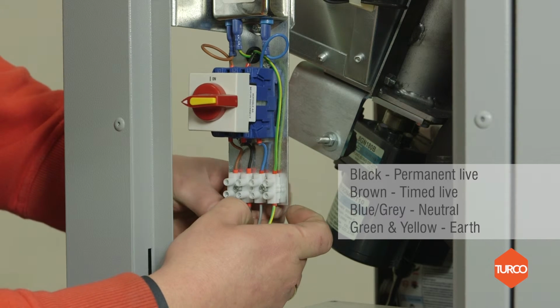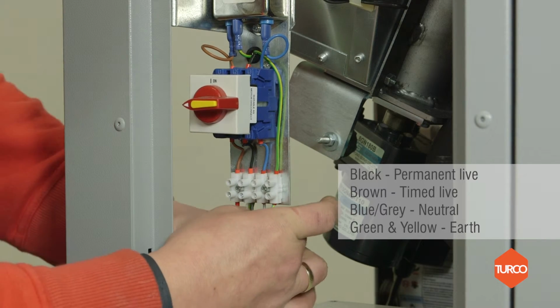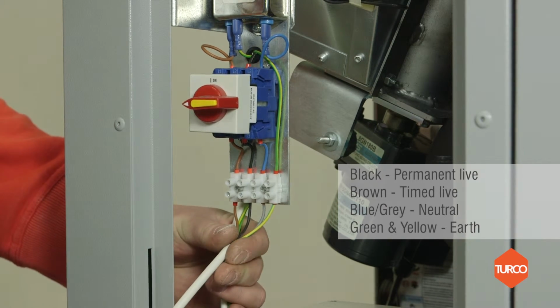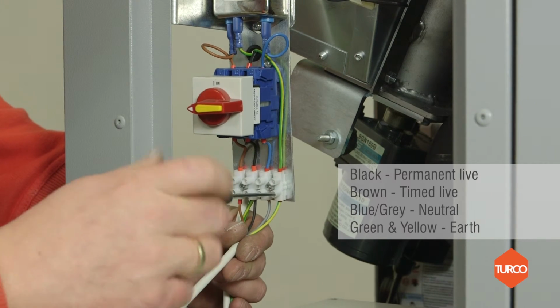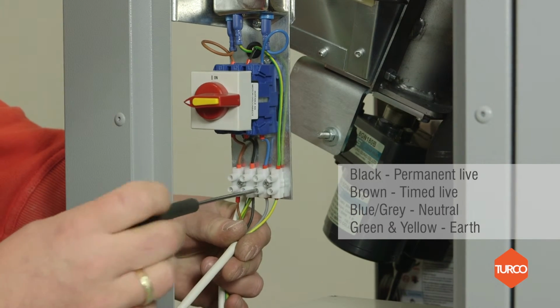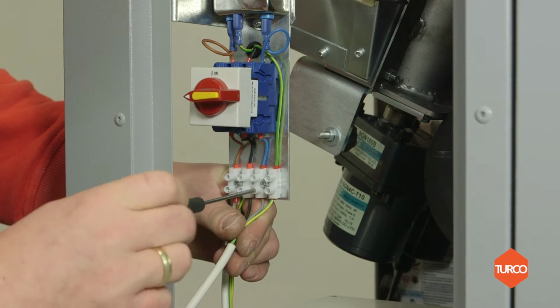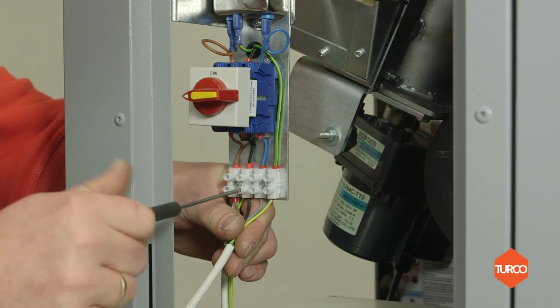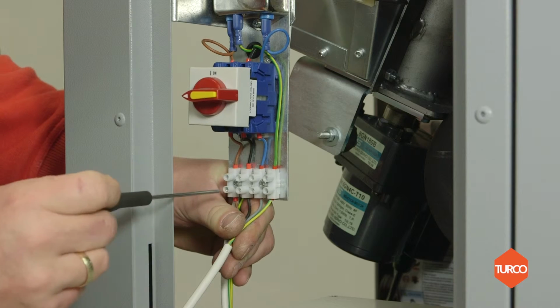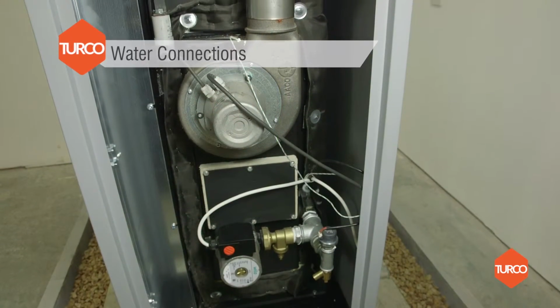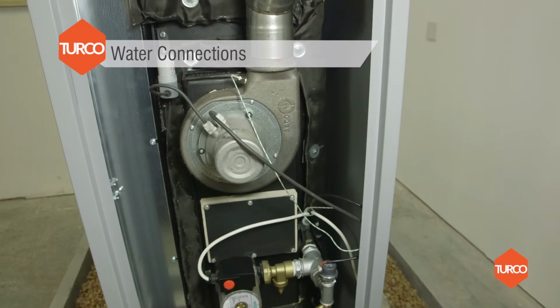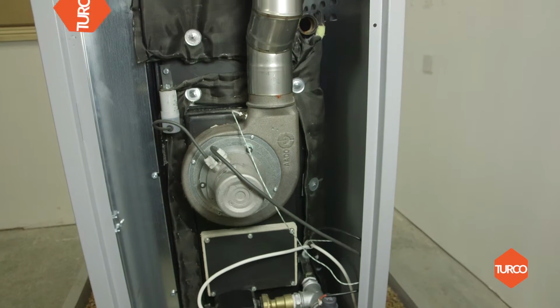Black is permanent live. Brown is time clock or controlled live. Blue or grey is neutral. Green and yellow is earth. The appliance must be connected to an electrical system which is equipped with an earth conductor complying with CEI 64-8. Water connections. The flow and return connections are on the right hand side of the boiler.